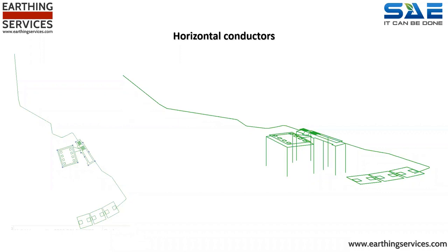Attached to the perimeter grading electrode were 11 number 10 meter by 120 millimeter diameter boreholes filled with conductive concrete. The depth ensured the electrodes sit within the optimum soil layer. Included within the design were connections to each foundation reinforcing to form an electrical circuit throughout. Earth bars were specified within the substation and the transformer room to facilitate earth connections for the main plant of this facility. The theoretical earth resistance of the earthing system, determined by the CDEGS software, was 0.453 of an ohm.